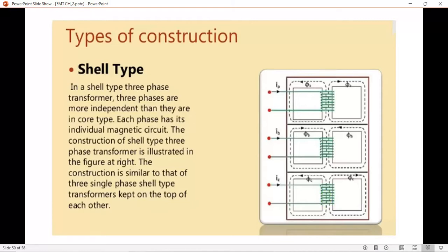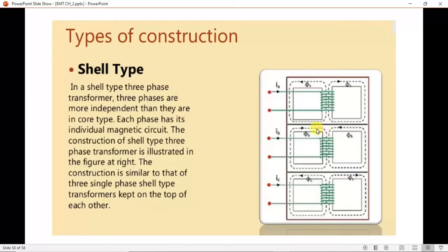Depending on the application, the high voltage and low voltage windings exist around the three main limbs. Like the core type transformer, the low voltage winding is near to the core. The two outermost limbs serve as flux return paths, and it is common for the outer limb and the yoke to be half the size of the main limbs. You can also decrease the transformer's height by reducing the yoke size.